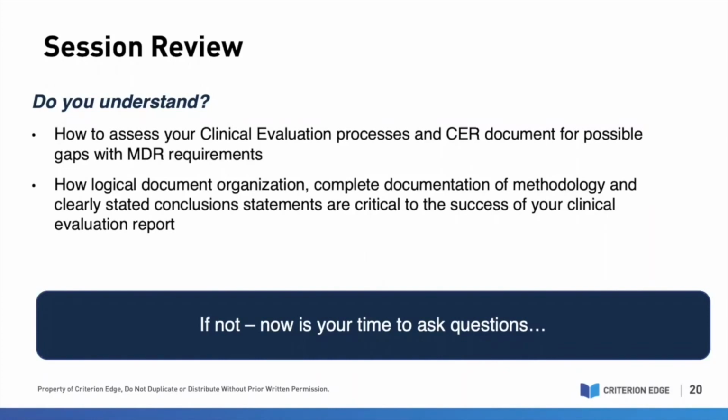Most of the MDR changes that you see within an MDR CER have to do with language and approach and analysis. It's not that the MDR CER has different sections than an MDD CER, so much as there's a different approach, and there's different language and different requirements set out in the establishment of safety and performance under MDR versus MDD. So no, you don't need a separate template, but you probably should look at your template, and I mean a template on its most high level scale.